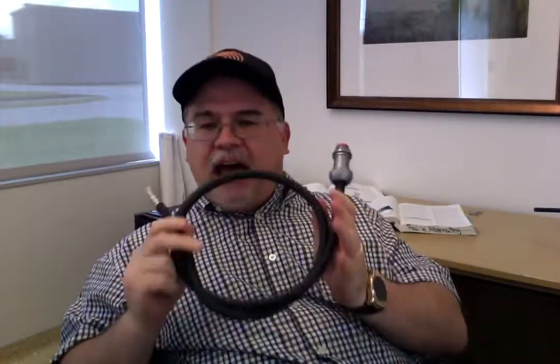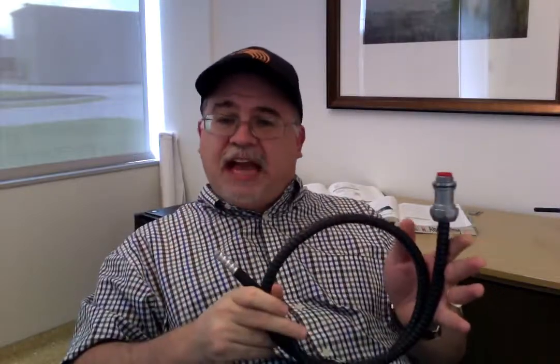Okay, so this is a wet location, good for use on parking decks. This is rated for direct burial. It'll be marked right on the side. I can put this in the ground. A lot of uses that I can use a PVC jacketed MC product in damp and wet locations. But that brings me to that word damp. Let's talk about that because that's the word that people don't want to talk about when it comes to MC cable. So let's dig in and discuss it a little bit. Maybe you can understand it a little better.